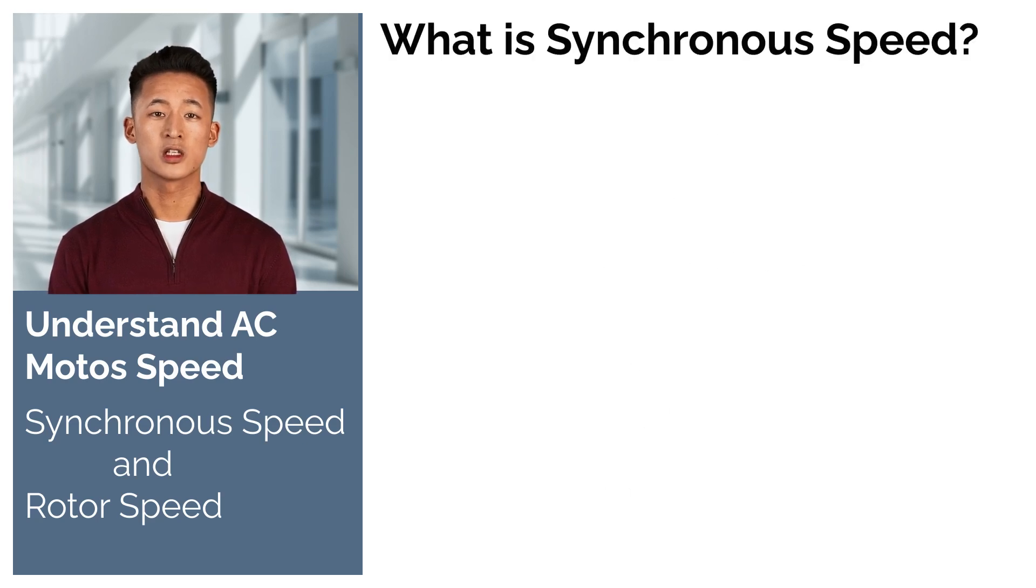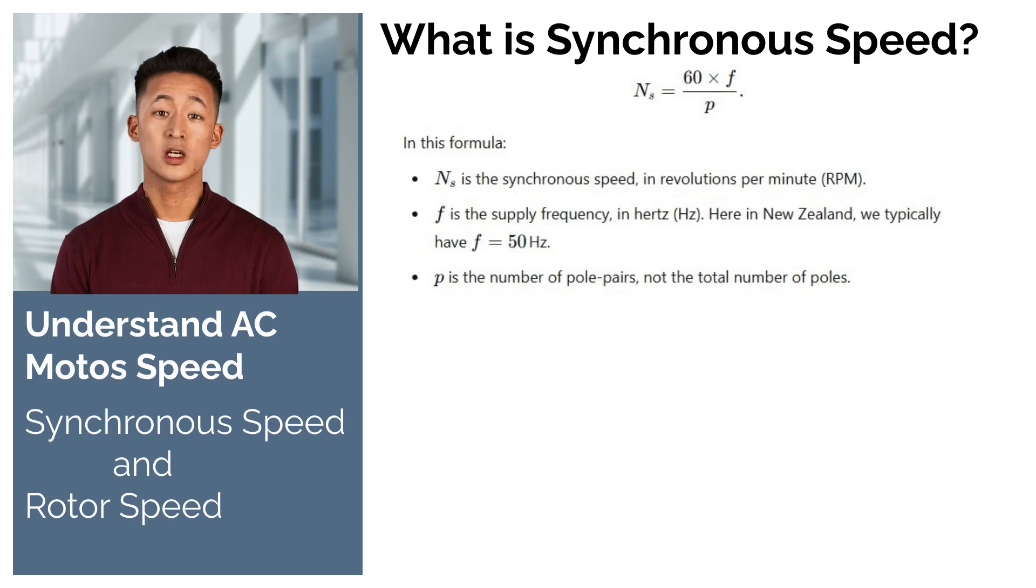What is synchronous speed? Synchronous speed is the speed at which the magnetic field created by the stator of an AC motor rotates. It represents how many times the magnetic field rotates per minute. The formula for calculating synchronous speed in an AC motor is: synchronous speed equals 60 times the supply frequency divided by the number of pole pairs.